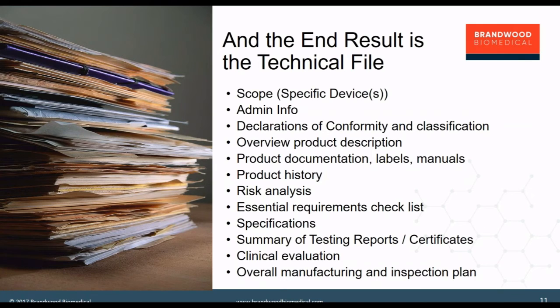in a summary form, or in a more expanded form in the case where some specific stages of your manufacturing process can have a direct impact on the compliance with the essential requirements. One example here is a product which has to be delivered sterile. It would be expected that such a product include in its technical file more in-depth information on the sterilization process and the controls which are in place as part of your manufacturing process. So all of that should be included in the technical file.